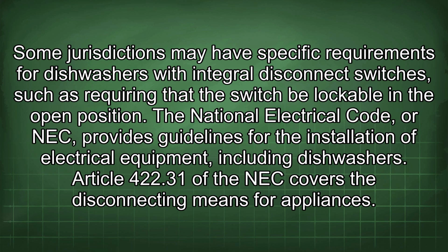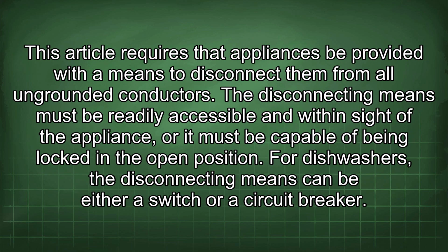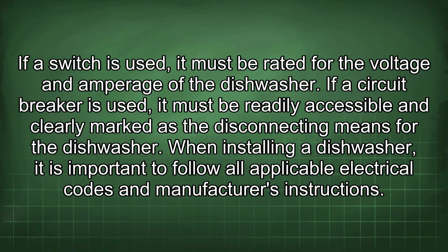Article 422.31 of the NEC covers the disconnecting means for appliances. This article requires that appliances be provided with a means to disconnect them from all ungrounded conductors. The disconnecting means must be readily accessible and within sight of the appliance, or it must be capable of being locked in the open position. For dishwashers, the disconnecting means can be either a switch or a circuit breaker. If a switch is used, it must be rated for the voltage and amperage of the dishwasher. If a circuit breaker is used, it must be readily accessible and clearly marked as the disconnecting means for the dishwasher.